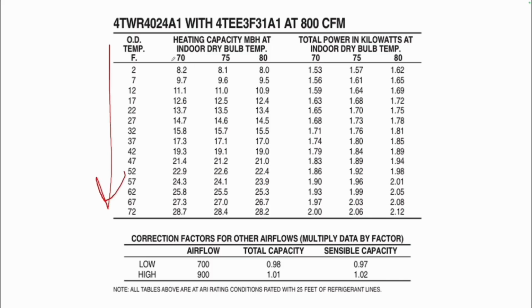And so we have our outdoor temperature on a vertical line here. And then as we go across the top, we have indoor dry bulb. So we have 70, 75, and 80. And we go down, let's say at 32 degrees, at 70 degree entering air, 15.8 would be 15,800 BTUs. Now notice below that, we have correction factors for airflow, low and high. So instead of 800 CFM, if we're at 700 CFM, we're actually going to adjust that capacity by multiplying it by 0.98. If we're at 900 CFM, we would multiply it by 1.01. So now you can see these correction factors.